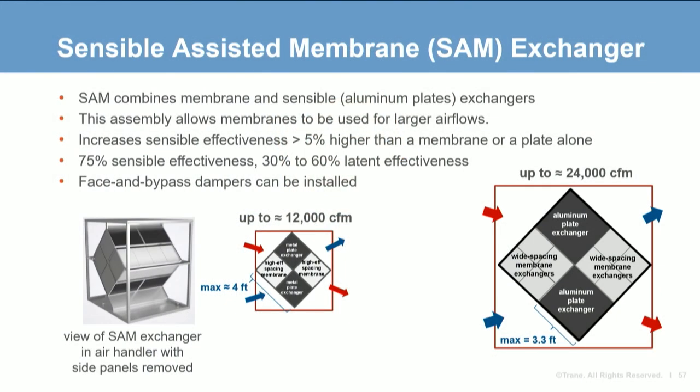SAM has the highest sensible effectiveness — 75% being typical — while achieving 30 to 60% latent effectiveness depending on conditions. The sensible plates actually enhance latent performance: the far membrane exchangers will have air pre-cooled by the upstream aluminum plate exchanger, which increases the relative humidity and thus increases the membrane's latent performance. No transitions or block-offs are needed. Unlike a bank of membrane exchangers, SAM uses metal plate exchangers to direct airflow to the second membrane, making it more usable in a typical air handler configuration and allowing the use of face and bypass dampers.